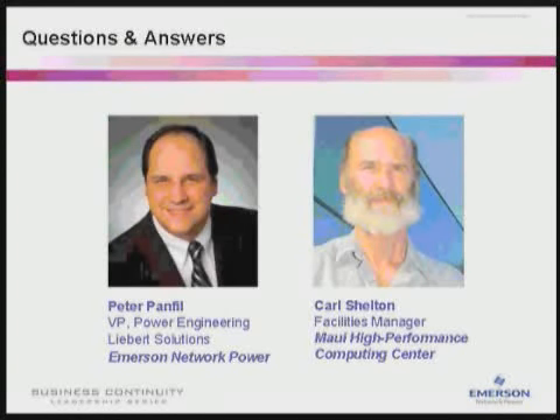We've also introduced a new way to dynamically adjust UPS capacity without adding additional hardware, and we call that soft scale. We've also seen some pretty dramatic changes in distribution technology. That distribution technology is evolving because customers are requiring more poles with larger branch distribution breakers to support the increasing number of high-density devices that they're adding to their data centers.